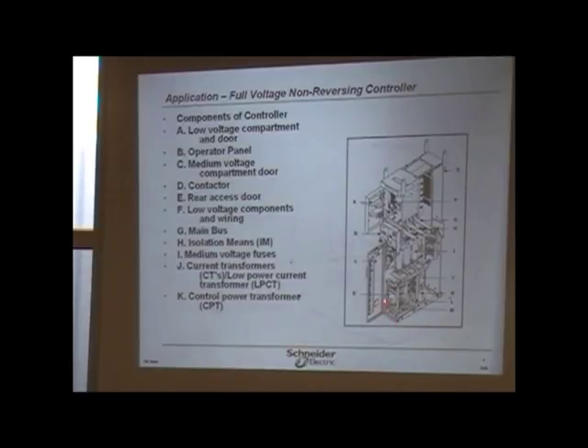But I do want to make you aware that this is the low voltage compartment up here, and that can be accessed when the equipment is running. It's this bottom part that cannot be accessed when it's running or in the on position. It's got, and I don't call it a fail-safe, but it's got an interlock that prevents you from opening this bottom latch door when the switch is in the on position.